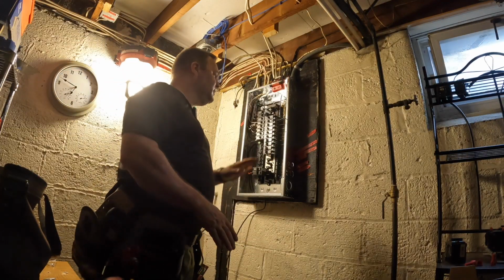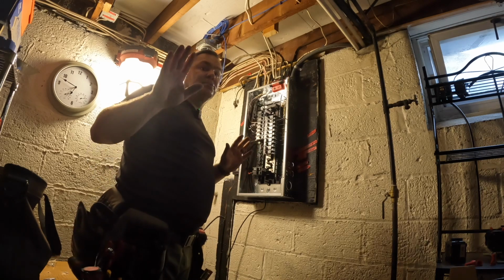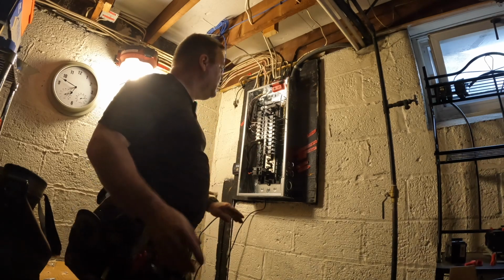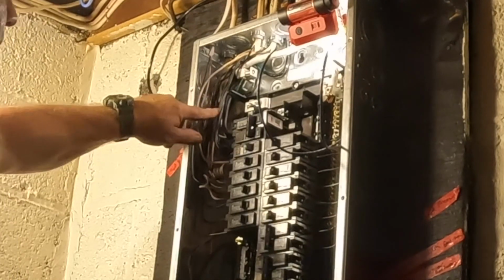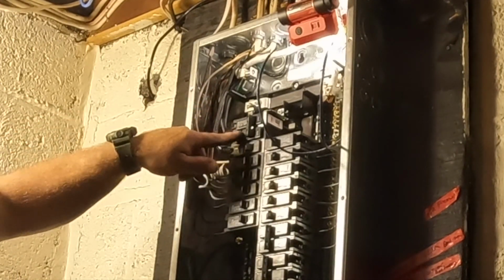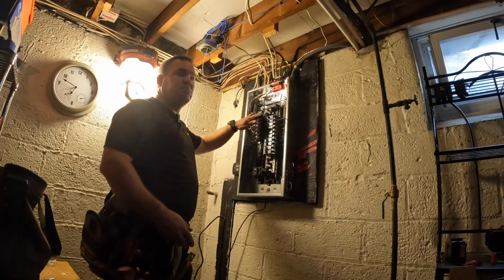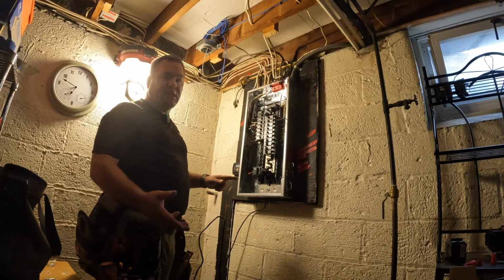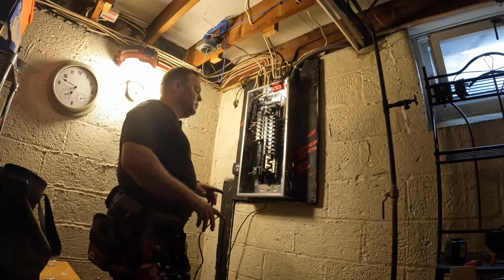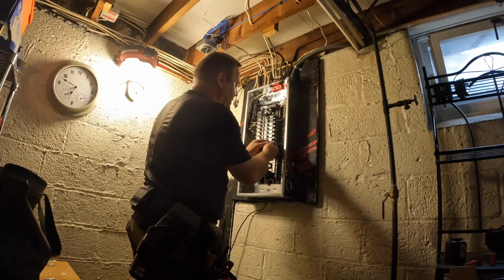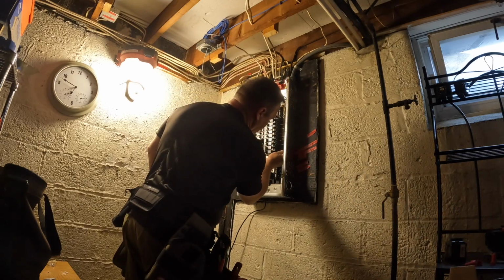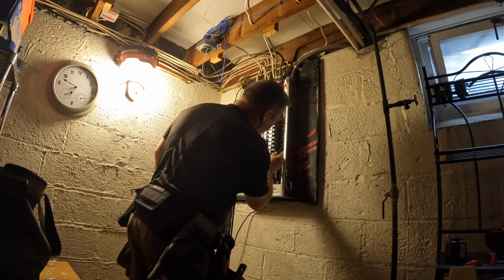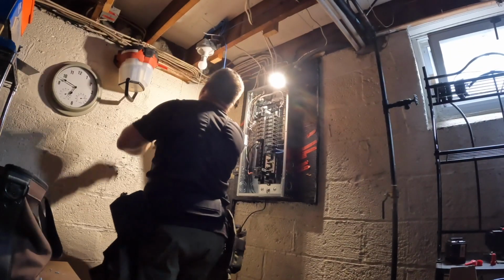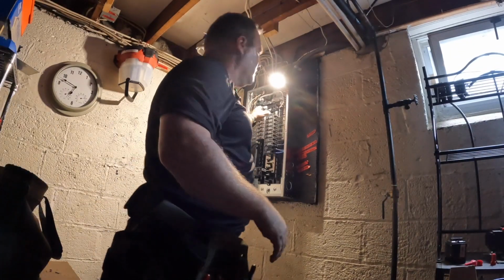Alright, now some of you might be wondering, gee, you put the meter in, is the panel live? The answer is, sort of. So power is coming in through these service entrance conductors onto the main breaker, okay? So once I turn this main breaker on, then the bus bar becomes energized, then we're back in business. But I just need to finish attaching this air conditioner, which is probably going to be the first thing that goes on. Okay, here we go.